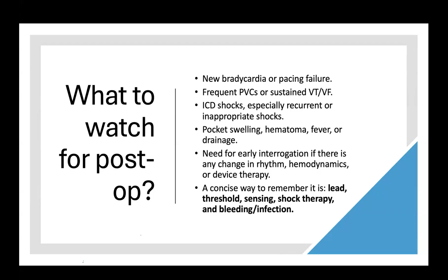seen on cardiac monitors. So to put it in a way that's easy to remember, we could say lead, threshold, sensing, shock therapy, and then eventually bleeding and infection. So we get to test the first parameter, which is the sensing of the pacemaker or an ICD. It's very essential to assess this sensing function because it helps with pacing and as a general parameter of lead integrity.